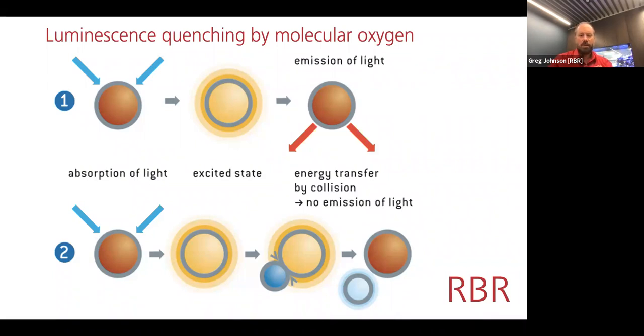Measuring at that rate is extremely challenging and requires a lot of power to the electronics. So there's another way of doing it, and that is to measure the phase delay between the pulse of light that you emit, that you excite it with, and that pulse and decay that is emitted. And the time delay between the two, because we don't excite with actually a single pulse, we excite with a pulse train or a sine wave, then you look for that phase delay between the sine wave of the incoming light and the outgoing light. And that phase is what is proportional to oxygen.